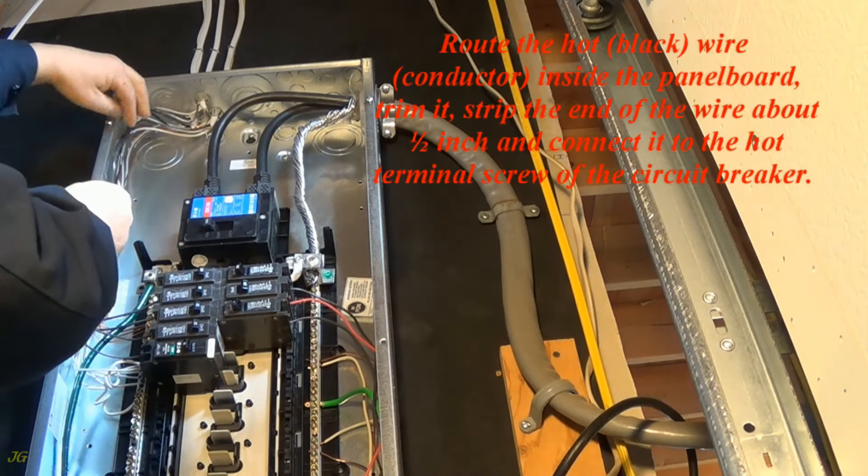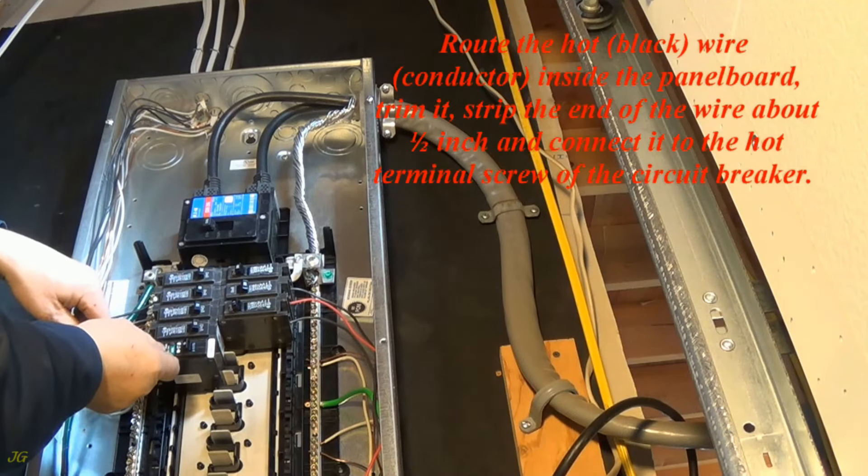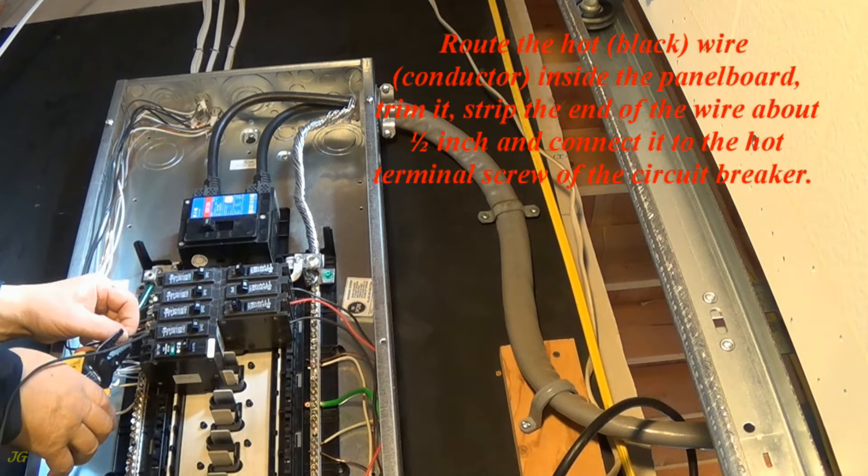Route the hot, black, wire conductor inside the panel board, trim it, strip the end of the wire about one half inch and connect it to the hot terminal screw of the circuit breaker.